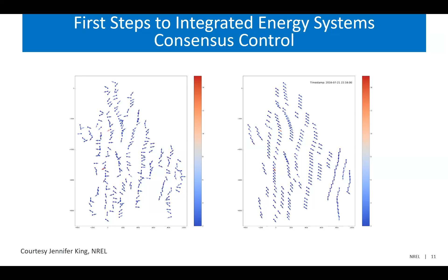One last example that points into the future: at my home office, the Flatirons campus at NREL, a remote site with some PV installed, some wind installed, some buildings on site with a load, and a large battery storage system. We were handed an opportunity to operate as an island when the single point of contact with our grid blew up, and we had a failure at our substation that pushed the Flatirons campus into an island.